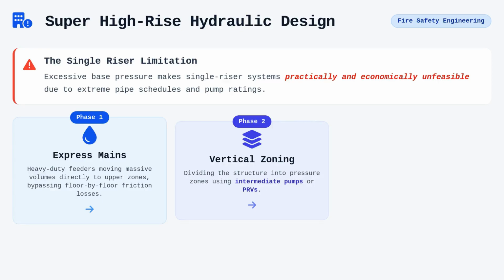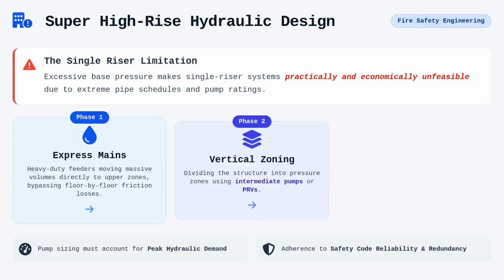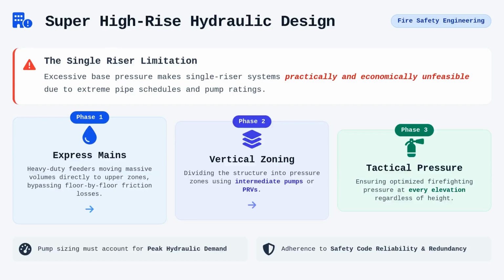You must understand how these components interact with the building's fire pump capacity, as the pump must be sized not just for the peak hydraulic demand, but for the reliability and redundancy requirements mandated by safety codes. Ensuring that firefighters have the tactical pressure they need at every elevation remains the ultimate goal of your engineering work.